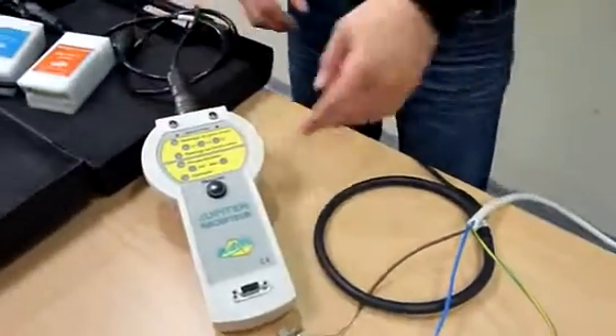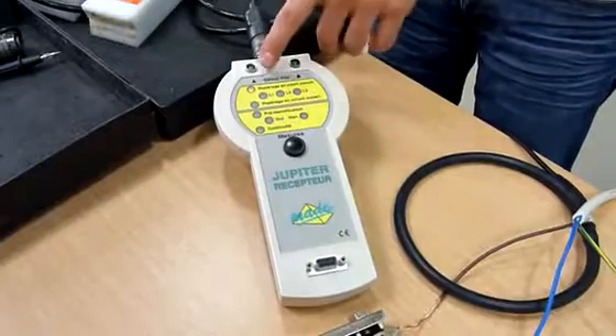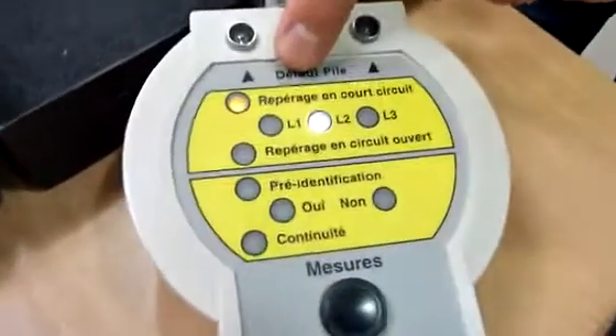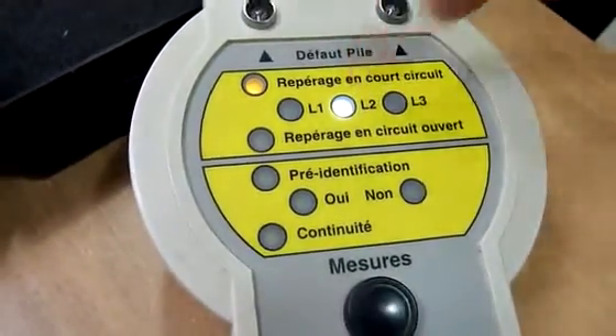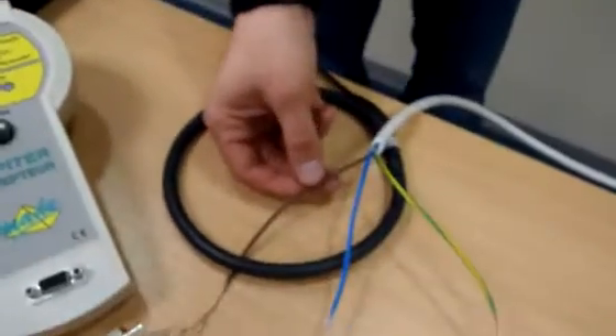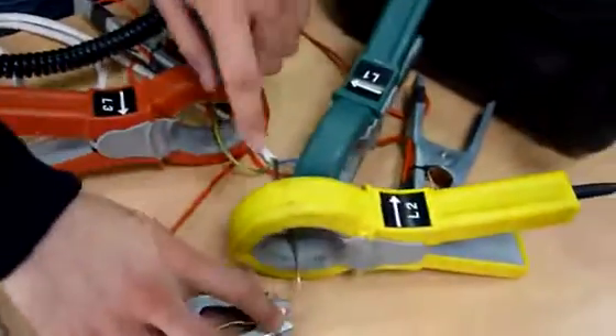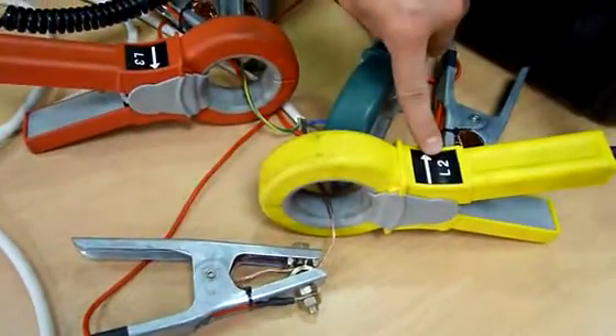It's very simple to use, you just push this button, and it says short circuit identification, then it says phase 2. So we say that the maroon one is phase 2, and if you come back here on the transmitter, you see that the maroon one is indeed phase 2. So at the same time you confirm that this is the right cable, and that phase 1 in this post matches phase 1 in the other post, because sometimes when you cut a cable and reconnect it, it's not connected properly.